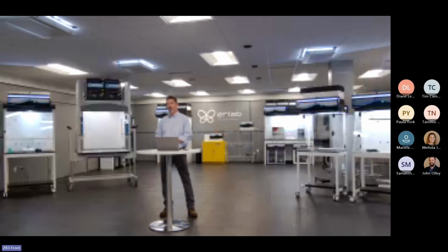Awesome. And how often do you need to change the carbon filters? That's going to depend on what you're doing. With the Halo, it's typically 18 to 24 months. For chemical storage, it's typically a year. Every year you want to change the filter. And then on the fume hoods, it's going to depend on the volume of chemicals you're using.